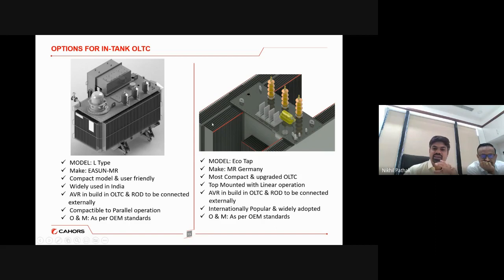Now, this Eco Tap OLTC is another upgraded version of the in-tank OLTC. This Eco Tap OLTC has a linear movement. It is installed on the top of the core coil assembly, and that is the reason the linear movement happens with a very compact design. So if you take an off-circuit transformer and an OLTC transformer, you will not find any difference in the sizes. Only the height will increase by 200, 300 mm. The length and width will remain the same compared with an off-circuit tap changer.